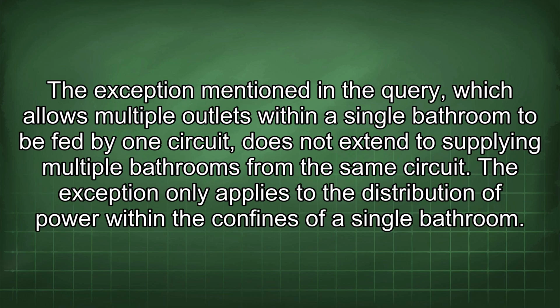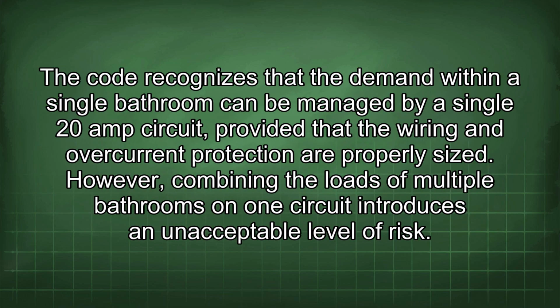The exception mentioned in the query, which allows multiple outlets within a single bathroom to be fed by one circuit, does not extend to supplying multiple bathrooms from the same circuit. The exception only applies to the distribution of power within the confines of a single bathroom. The code recognizes that the demand within a single bathroom can be managed by a single 20-amp circuit, provided that the wiring and overcurrent protection are properly sized. However, combining the loads of multiple bathrooms on one circuit introduces an unacceptable level of risk.